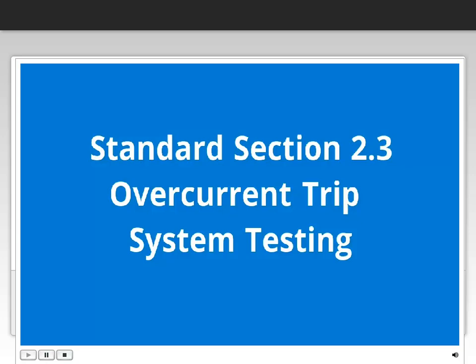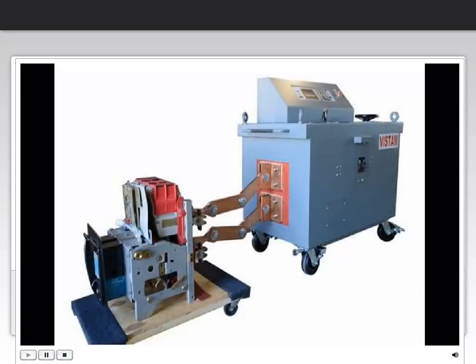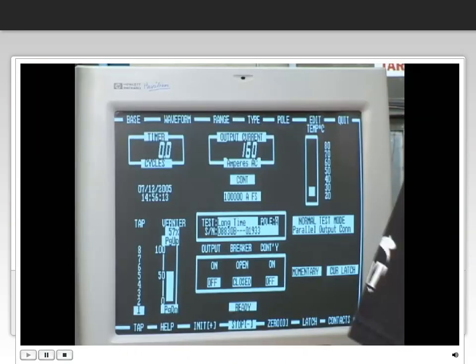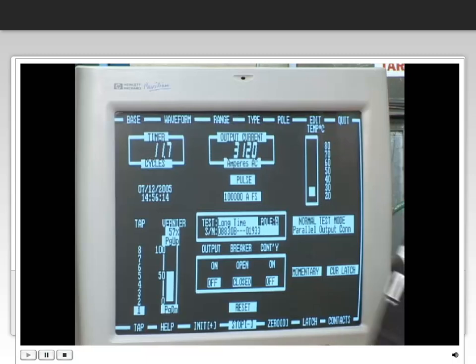In the next step, a high current primary injection test set is connected to the breaker. Primary injection testing is the best way to verify the operation of the trip unit since it exercises every aspect of the breaker and trip unit, including the CTs. Secondary injection testing bypasses the CTs. And finally, we are verifying the breaker trips in conformity with the manufacturer's guidelines with the primary injection test.